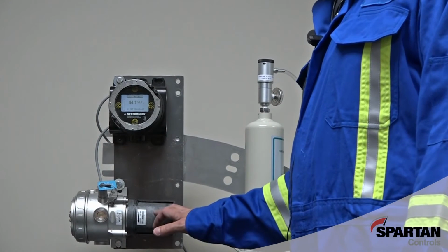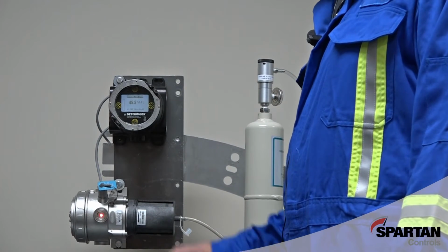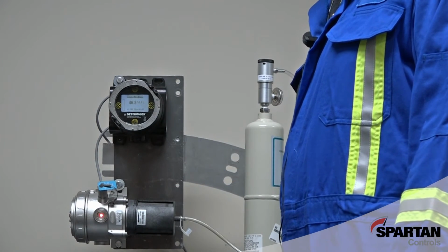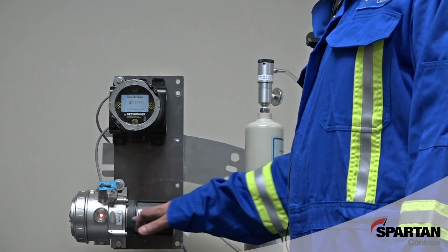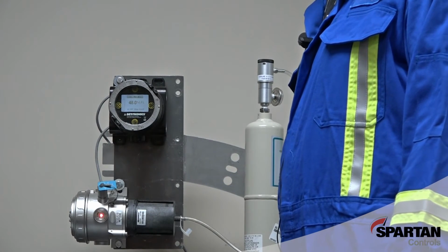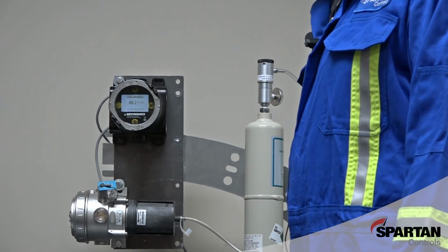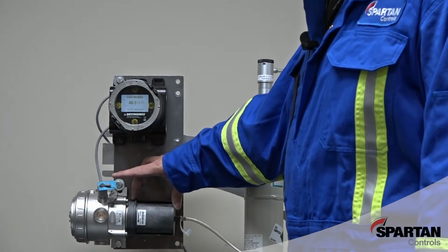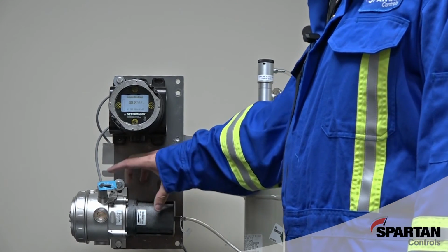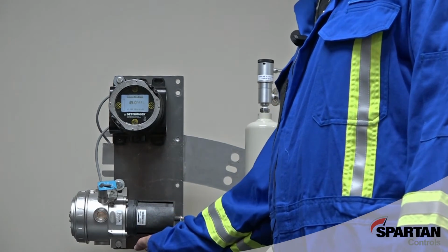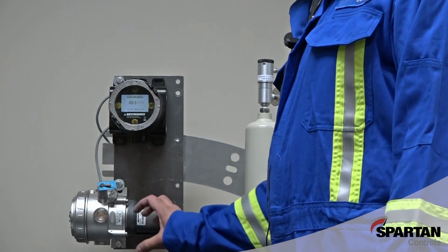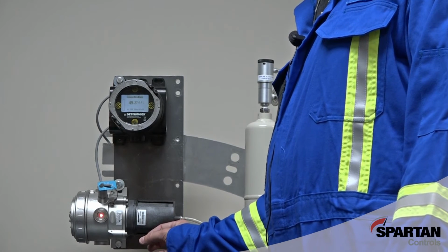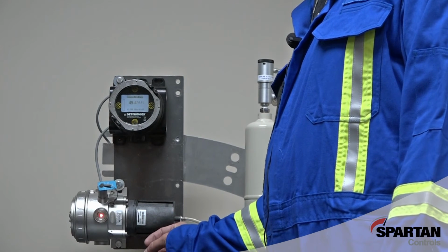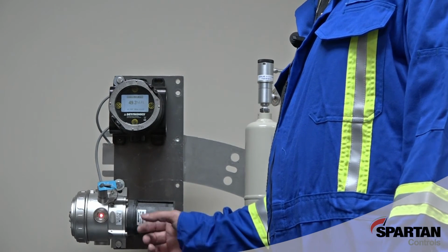And while the device is going through its span calibration, I'd like to take a minute and talk about the orientation of the detector. As you see here, this is the correct orientation as per the manufacturer. And there are a couple of reasons for that. First off, you increase your detection space. If you had it mounted vertically, your detection space would be very narrow. Also, vertically, the detection area works as a trap for dust, dirt, and debris, which can cause a fault and be troublesome to your control room.